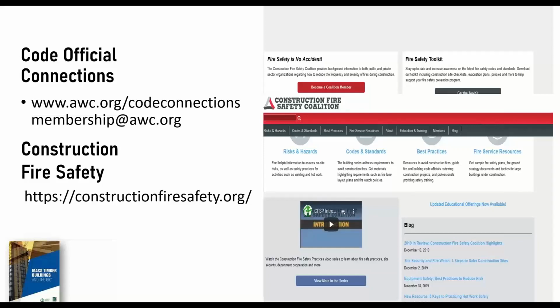Yeah, so there was testing done for typical penetration. So don't be concerned as a designer about E814 penetration or ASTM penetration tests. There are rated assemblies and tested assemblies that permit penetrations of the mass timber elements. But just like in a heavy timber building, concealed spaces aren't really all that prevalent. So we envision a lot of visible ductwork, installed bundles, that sort of thing. It seems that every chain quick dining restaurant I go into now has ductwork hanging off the ceiling.